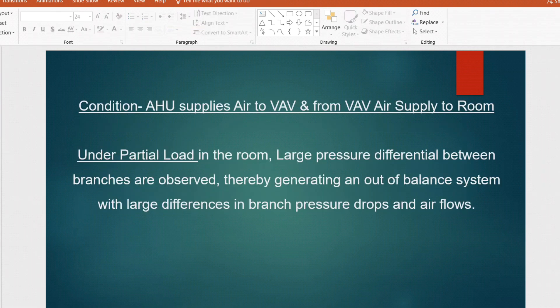The next question: we have a project where different room indoor temperatures must be maintained and VAV systems are installed. The air handling unit supplies air to the VAVs and from the VAV air is supplied to different rooms. Under partial load in the room, you can see the minimum and maximum flow mentioned in the VAV. The question is: under partial load, large pressure differentials between branches are observed, creating an out-of-balance system with large differences in branch pressure drop and air flow.